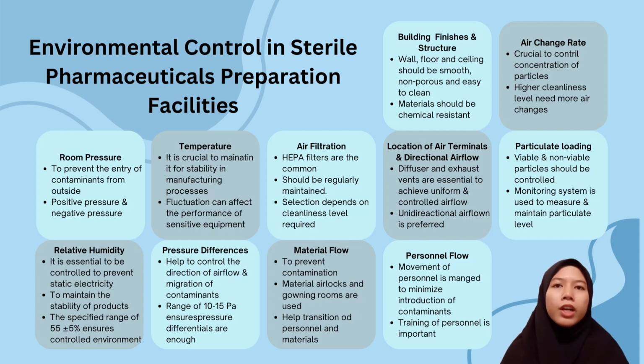Then, location of air terminals and directional airflow. Strategic placement of air terminals ensures uniform and controlled airflow within the room. It should establish specific airflow patterns to prevent the accumulation and spread of contaminants. Then, room pressure. Positive pressure is maintained in clean room to ensure that air flows out of the room and prevents the influx of particles. Negative pressure may be employed when there is hazardous substance within the room. Next, particulate loading. It refers to the concentration of airborne particles in the clean room. Monitoring systems like particle counters are used to measure particulate levels within acceptable limits. Then, temperature.